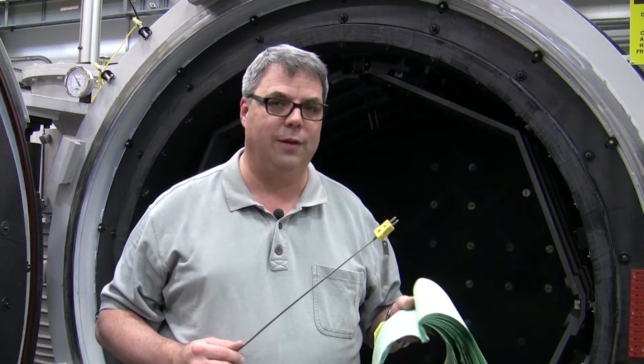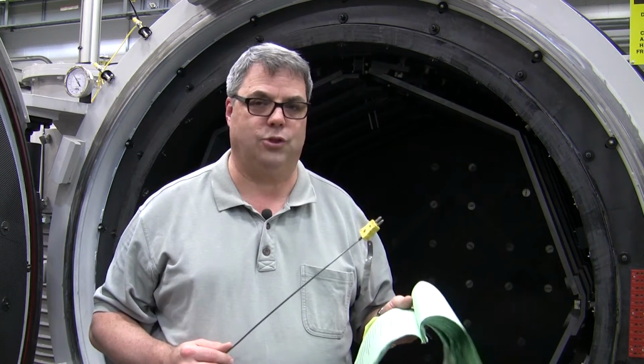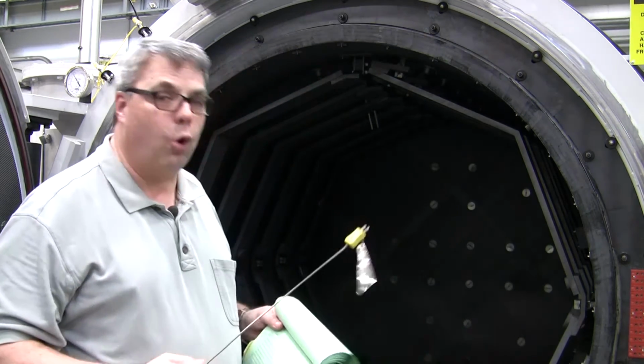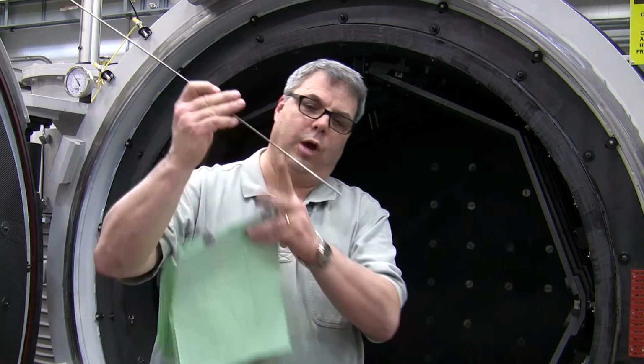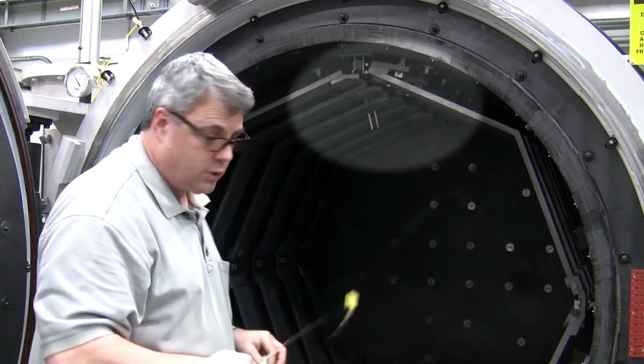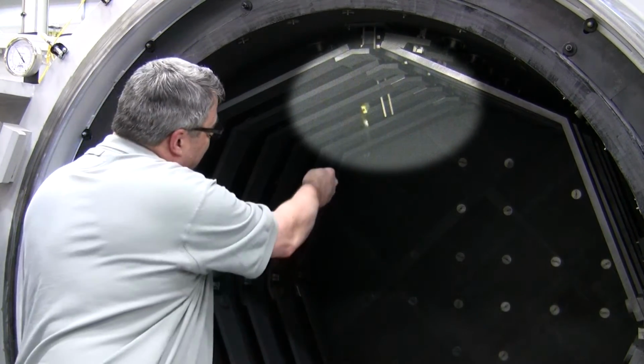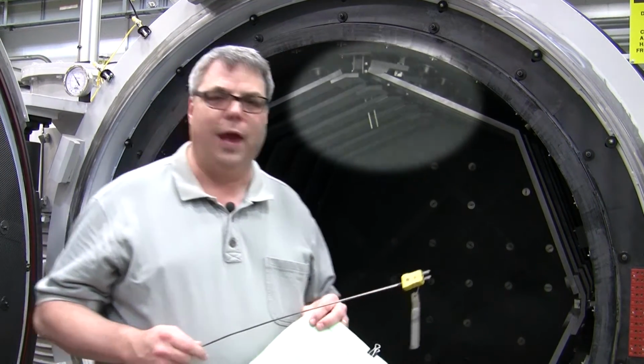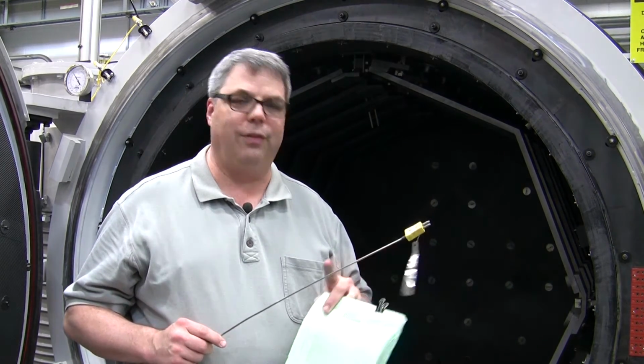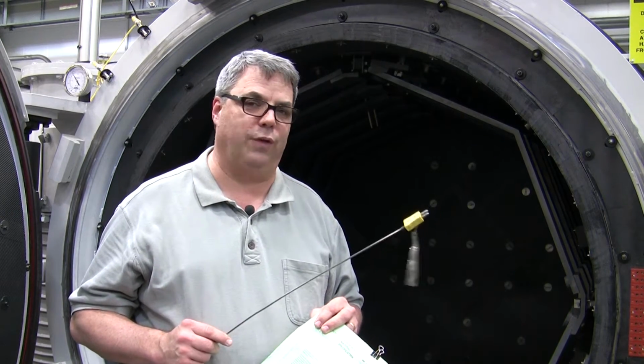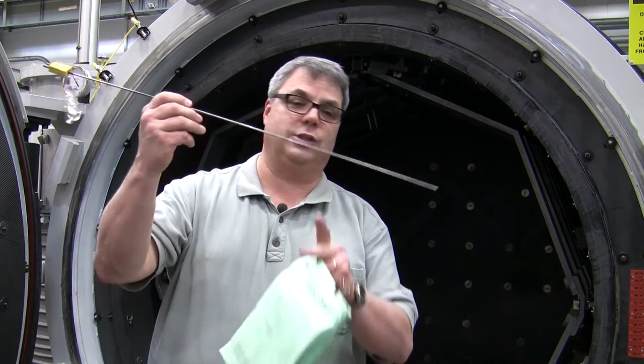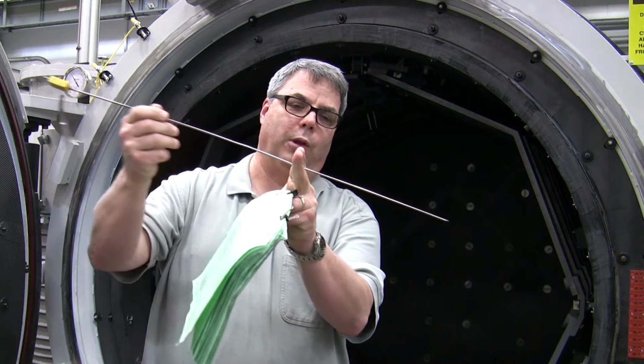The inverse to that is I've seen customers and inspectors that say, no, you don't have to recertify the machine, as long as after the survey you have recorded the as discovered and as found thermocouple immersion depth into the furnace. A general rule of thumb for most furnace applications is the tip of the control TC is normally 2 to 3 inches past the surface of a heating element. That's a good starting point. And then from there, you do your temperature survey, you balance the heat load across the hot zone, and when you're all done trimming the survey as tight as you possibly can get it, then you go back to your set point. And if my set point number 1 is 1,000 degrees Fahrenheit, and I have a spread throughout the hot zone load of plus or minus 5 degrees, but it's deviant from the control set point temperature, then I adjust the control TC, and I either have to push it further into the hot zone or pull it further out to bring the load up or down to match the tip of the thermocouple.